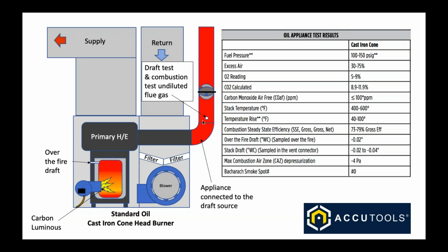We're looking at several things. Again, we want to make sure our stack temperature is in a safe range of 400 to 600 degrees. Temperature rise is right, efficiency is right. And more importantly, we want to make sure that we have the input correct and the draft correct.